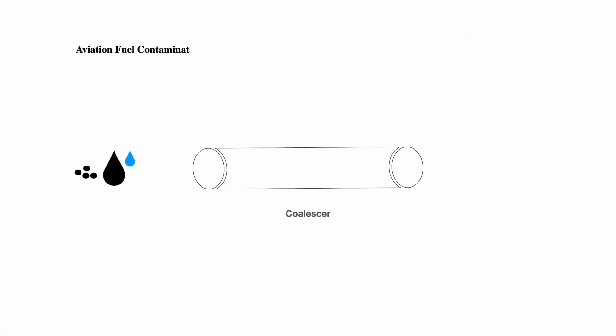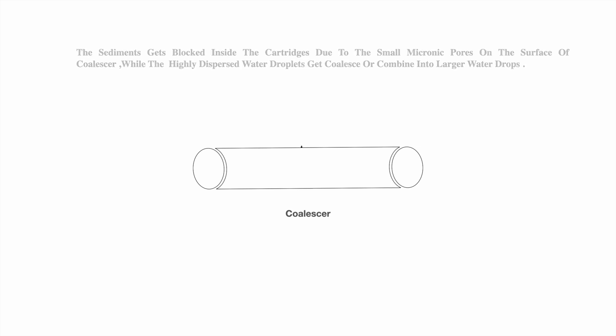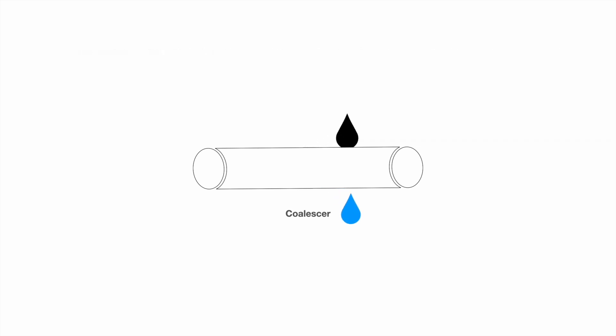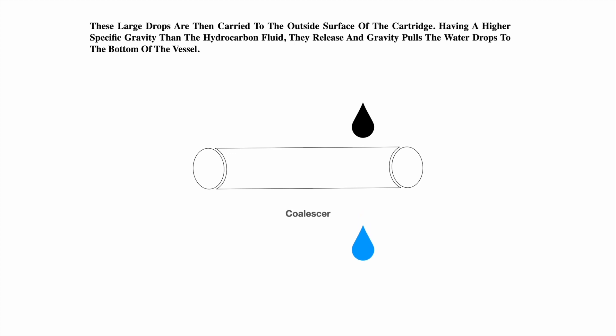Aviation fuel contaminated with water droplets and sediments enters inside the coalescer elements. The sediments get blocked inside the cartridges due to the small micronic pores on the surface of the coalescer, while the highly dispersed water droplets coalesce or combine into larger water drops. These large drops are then carried to the outside surface of the cartridge. Having a higher specific gravity than the hydrocarbon fluid, they release and gravity pulls the water drops to the bottom of the vessel.